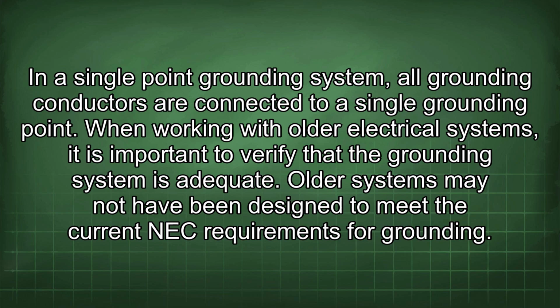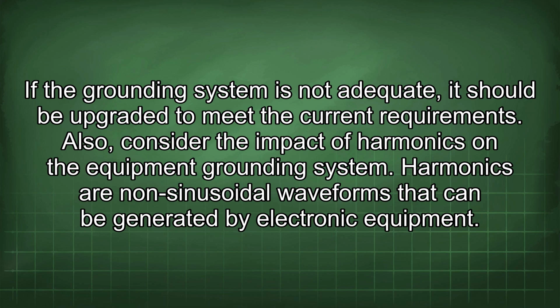When working with older electrical systems, it is important to verify that the grounding system is adequate. Older systems may not have been designed to meet the current NEC requirements for grounding. If the grounding system is not adequate, it should be upgraded to meet the current requirements. Also, consider the impact of harmonics on the equipment grounding system.